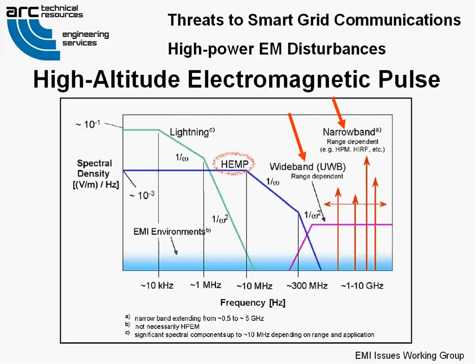High-altitude electromagnetic pulse, or HEMP, is composed of three time frequency segments. Early time E1 HEMP travels at the speed of light from the explosion and reaches field strengths of 50 kV per meter within 10 nanoseconds. Its spectral density versus frequency is shown by the blue line. Intermediate time HEMP reaches 100 volts per meter from 1 microsecond to 1 second later, and late time HEMP reaches 40 volts per kilometer at 1 to several hundred seconds after the event, which is similar to geomagnetic storms.